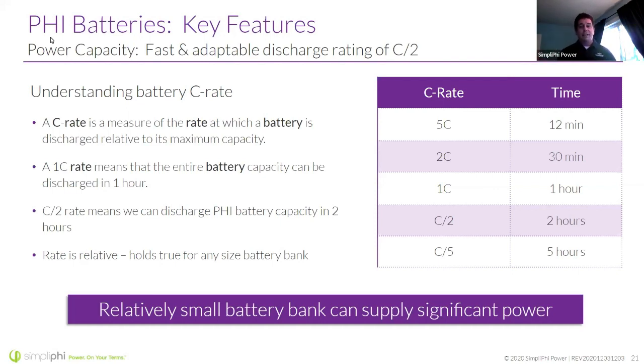A bigger thing for a lot of customers is that you can charge quickly. In winter, with fewer sun hours in the Northern Hemisphere, if you're charging from solar, you only have so many hours in the day. Or maybe you're running a generator, and increased generator output for a shorter duration saves you on fuel costs. Instead of running that generator for 5 hours, you can get the charging cycle done in 2. Or maybe you're pulling from the grid and want to avoid a lot of kilowatt hours during peak hours. You can get that charge done quickly. So it's really important to understand the C rate of a battery, both for design and for functionality for your end user. What is it going to take to recharge this battery, and how long will it take?